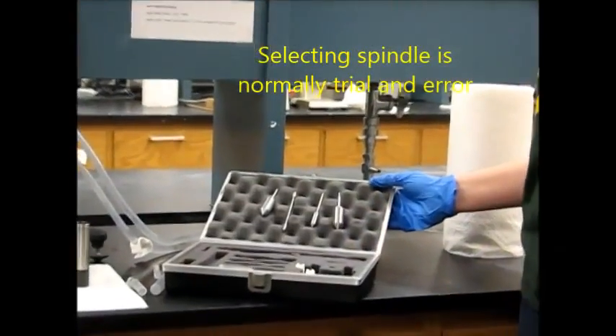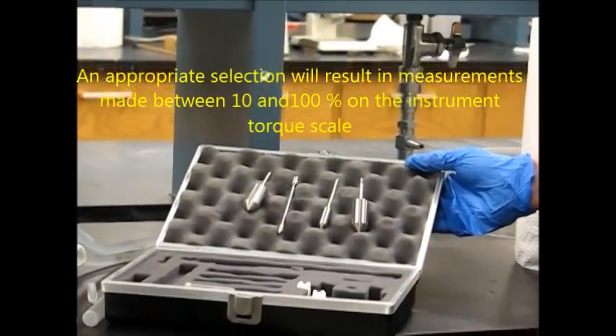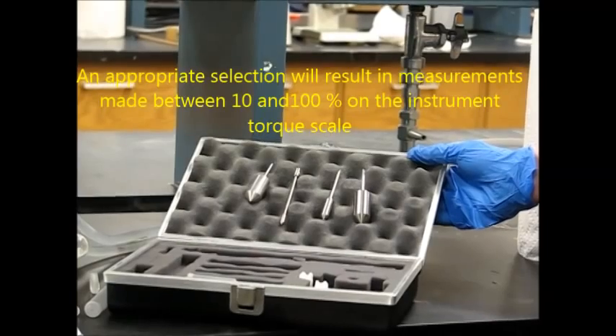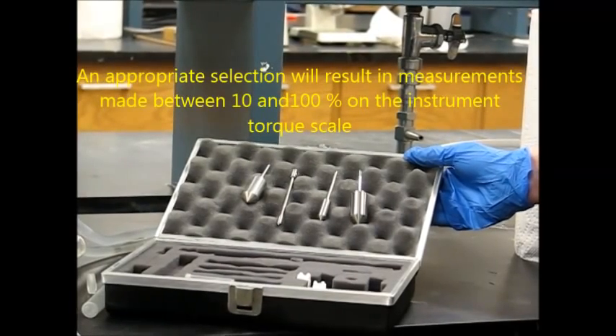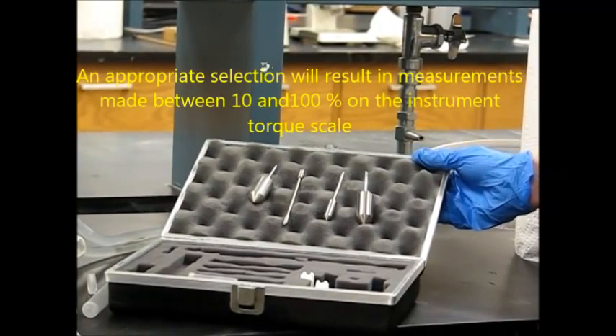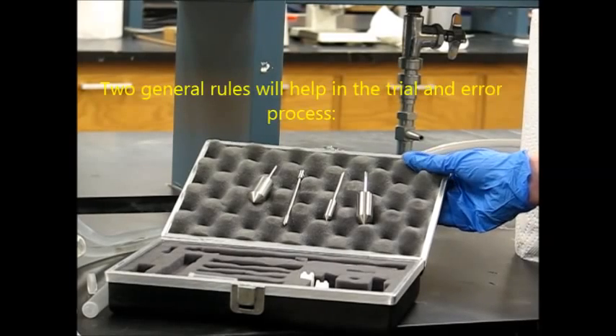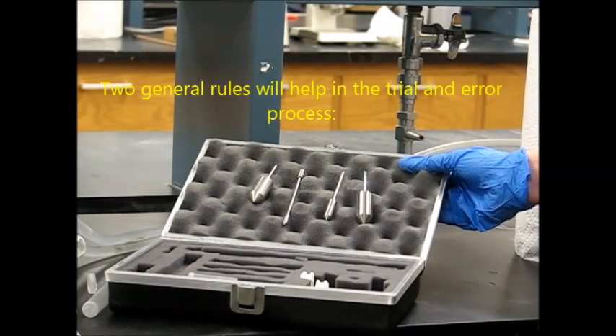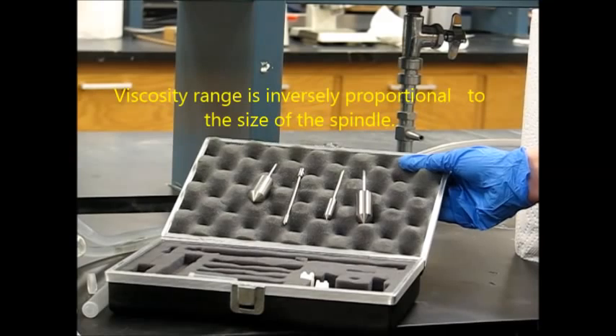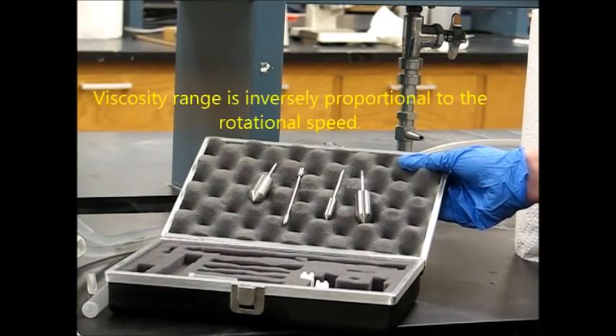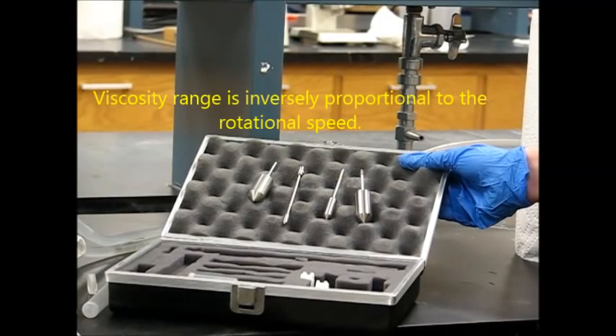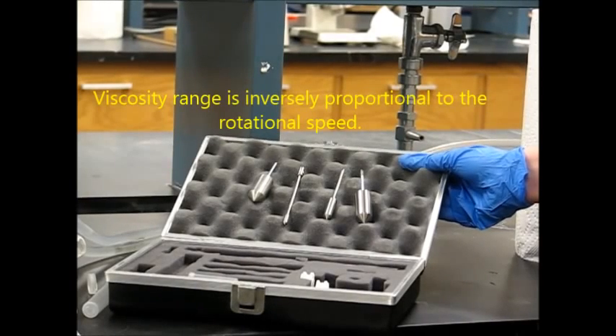Selecting a spindle is a trial and error process. An appropriate selection will result in measurements made between 10 and 100% on the instrument torque scale. These two general rules will help in the trial and error process. First, viscosity range is inversely proportional to the size of the spindle, and second, viscosity range is also inversely proportional to the rotational speed.